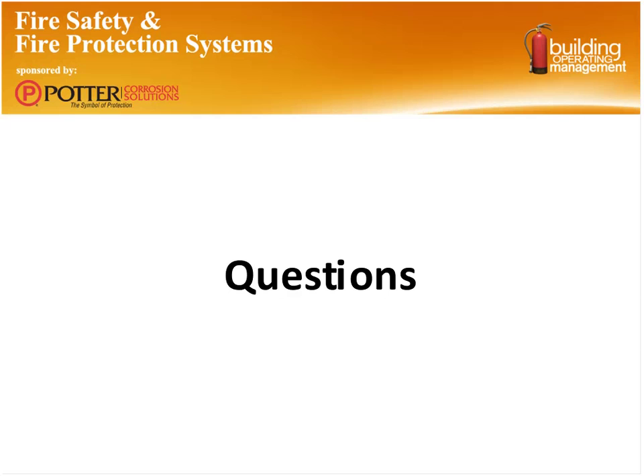Good idea, though. Okay. Speaking of UL, is there a UL listed or FM Global approved corrosion monitoring system? And if so, does corrosion monitoring replace the NFPA 25 5-year internal inspection on wet sprinklers? You know, there are some corrosion monitoring systems. I think Potter has one. I think it's really a discussion that has to happen with, I guess my depth of knowledge on the actual corrosion monitoring systems is not that great. So I would like to say probably defer that to Potter or one of the other manufacturers that do make the actual components. Okay.